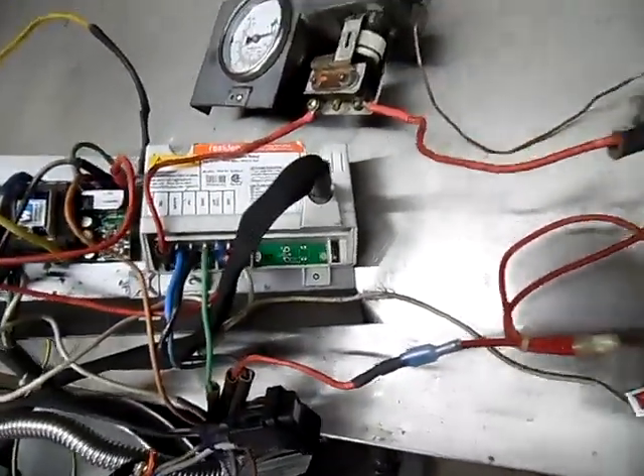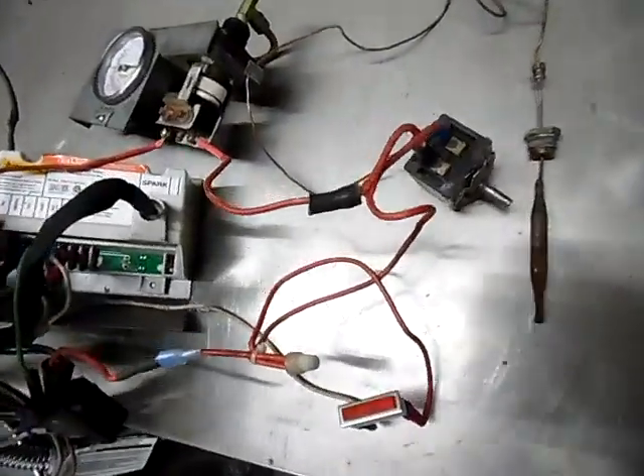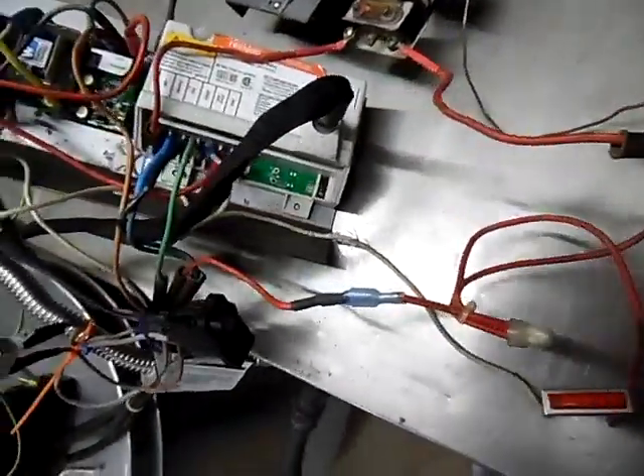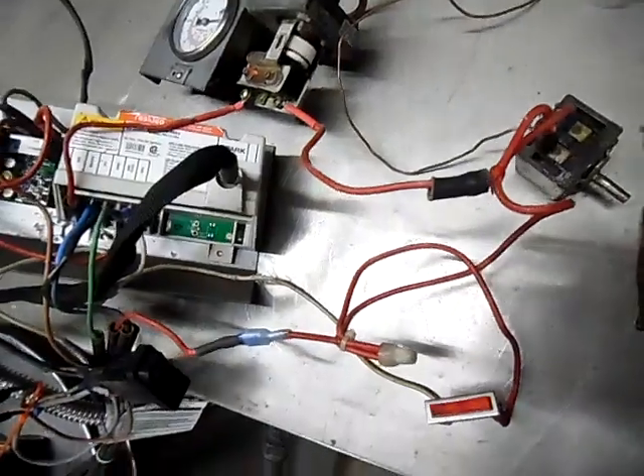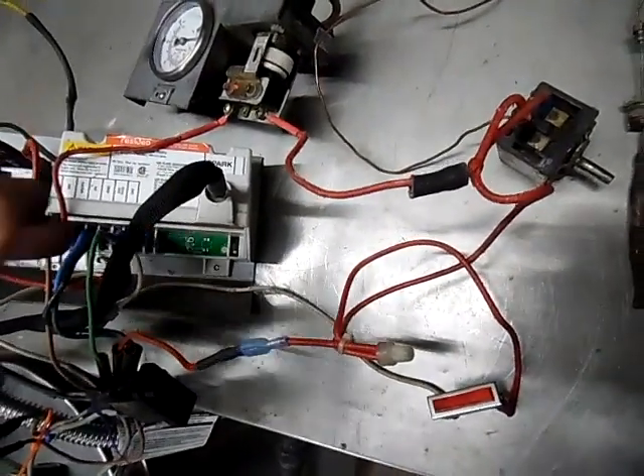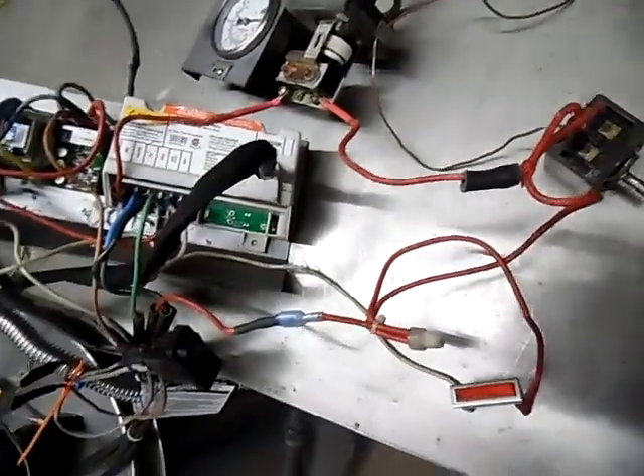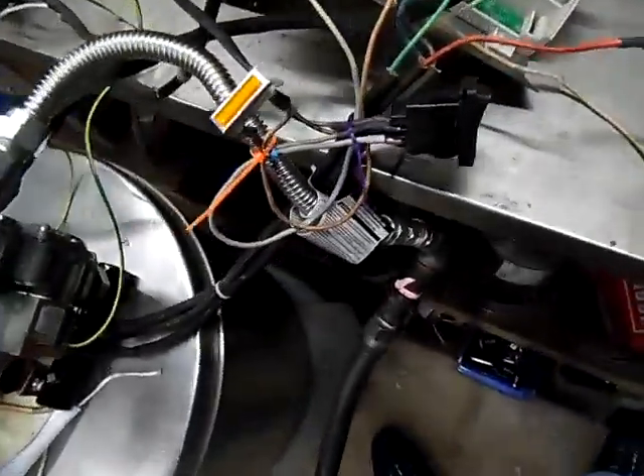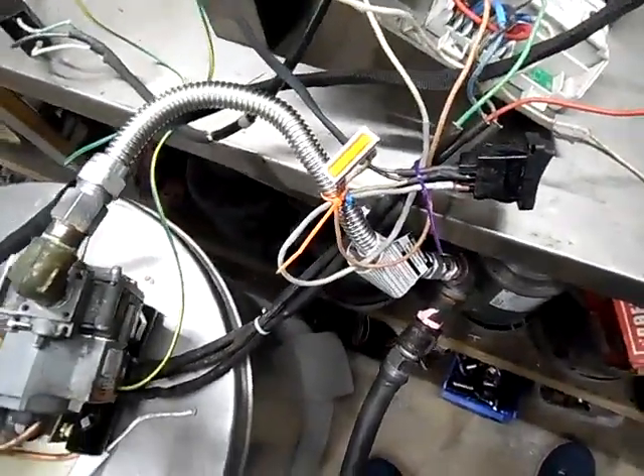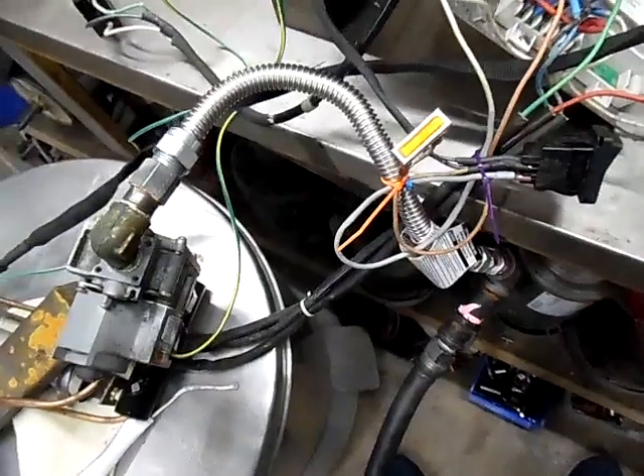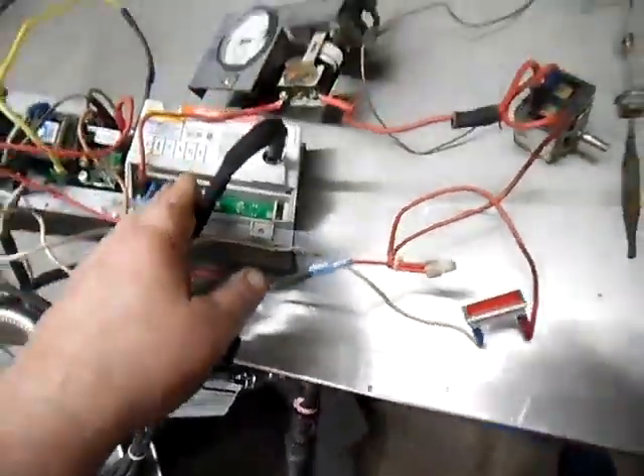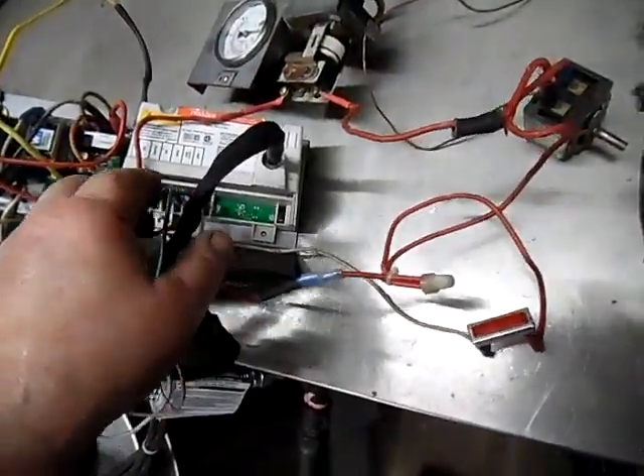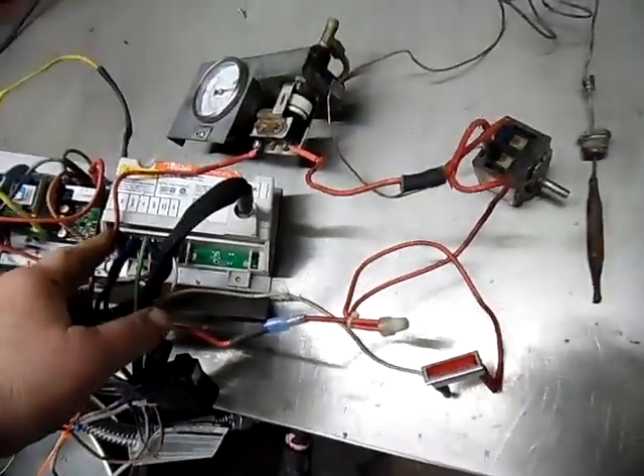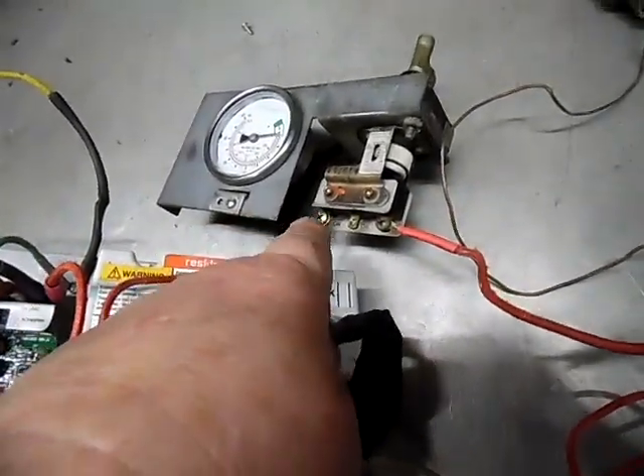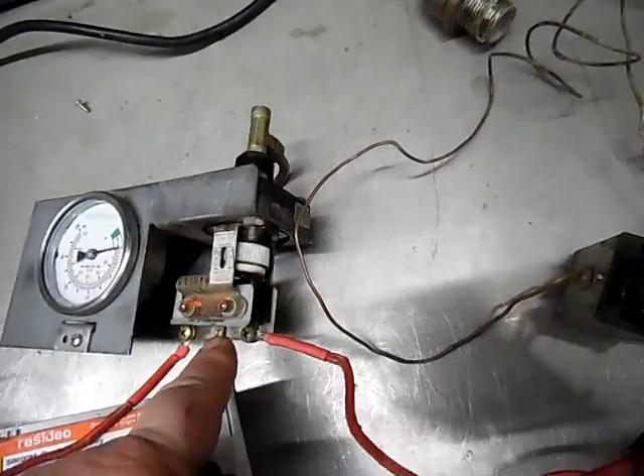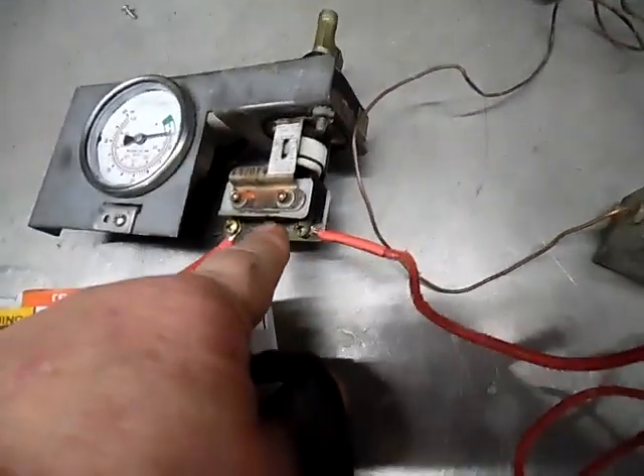Immediately, what it's going to do is, if there's a call for spark to the pilot, immediately once you get through the cycle, and it happens within seconds, this thing will ignite and you'll start hearing the spark at your pilot. Then once the pilot lights, like I said before, it's going to read the sense, and immediately you're going to get the MV to energize inside the box, and it will send 24 volts right through this red wire into our pressure switch. Now this pressure switch is a safety.